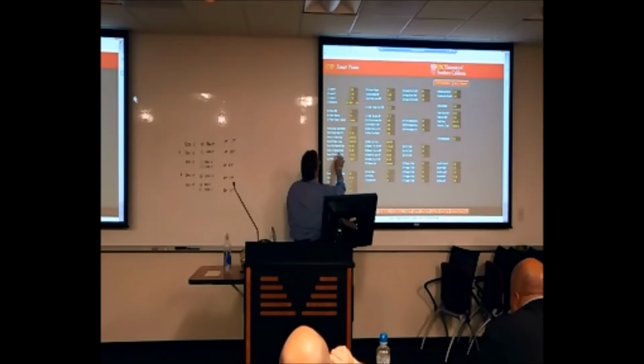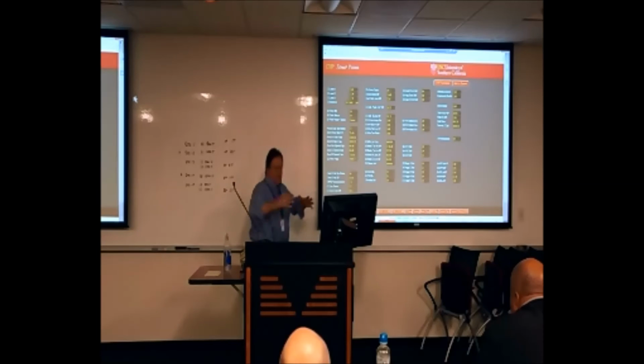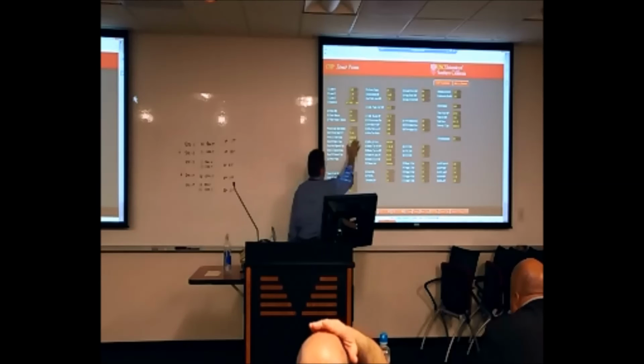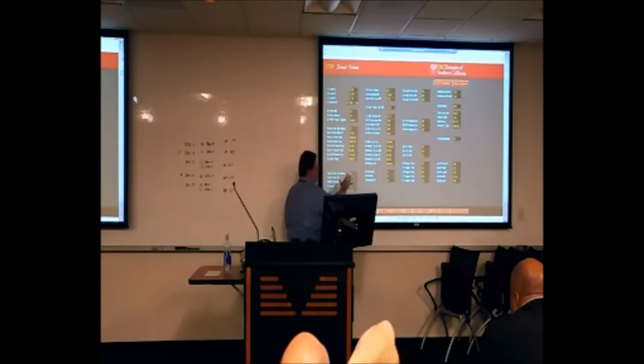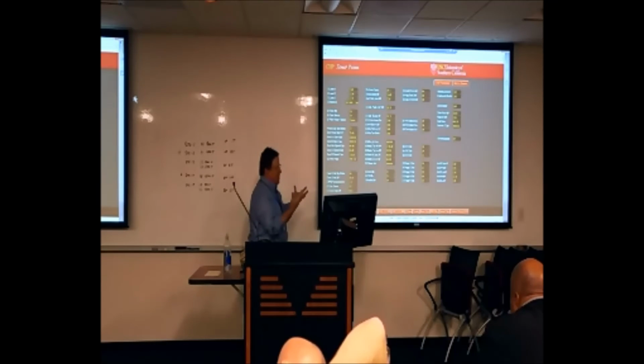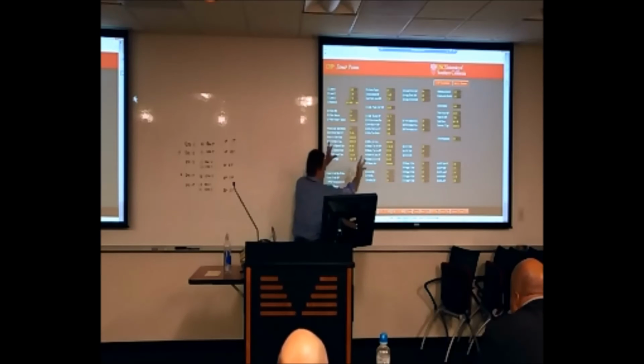We also have speed caps on this. So when we bring on the next pump, if we're in the DP control scenario, the variable speed scenario, it's going to jump up to a 65% low speed cap just to get the pump out of the box and sped up. And then it's going to start adhering to its GPM and to its delta T control. So when the additional pump starts, it just rockets to a fixed speed right away to get up and get pressure, and then the other control begins to take place.